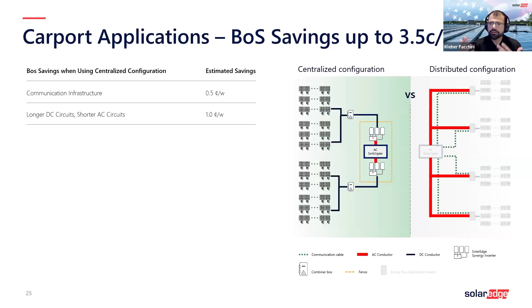Because now all of your combining is done with DC combiner boxes out in the array, bringing everything together and combining as much as possible in the DC before the inverters co-located, you now have the opportunity to use larger inverters and therefore fewer inverters for your project. You're able to save 2 cents a watt, not only from using fewer inverters but also saving on AC balance of system. So the total savings is about 3.5 cents a watt.